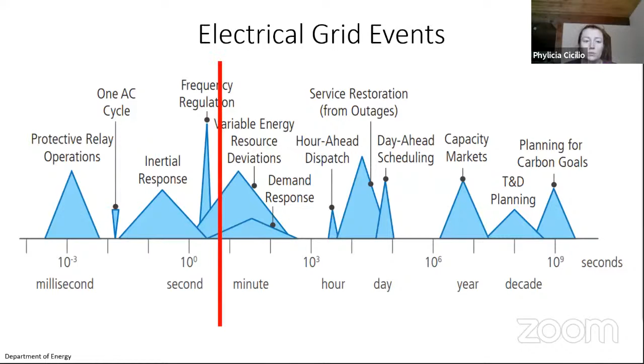So how are we defining steady state versus dynamic simulation or modeling? In steady state, you use power flow analysis, which can be used for energy balance problems and dispatch. If you are looking at dynamics, additional models are needed, typically modeled using differential algebraic equations, used to model dynamic components such as generators and dynamic loads, like power electronic loads and motor loads such as large fans. There are various levels of these more detailed models.